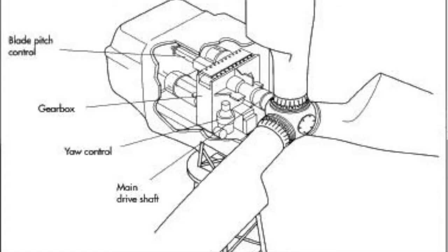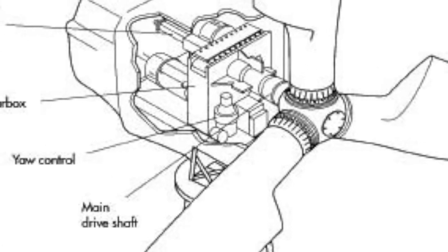Anemometers and wind vanes are now used to measure the speed and direction of the oncoming wind so that the wind turbine can reposition itself using a yaw motor. The wind turbine can then face the wind directly to make the maximum amount of energy. The next feature of the wind turbine is the gearbox, which enhances the relatively slow speed of the spinning blades, 16 revolutions per minute, to a massive 1,600 revolutions per minute. This makes it possible for the drive shaft to speed up.